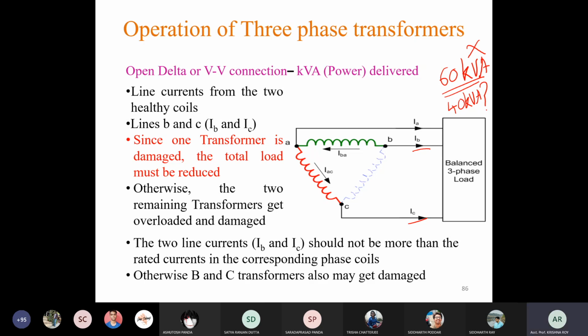So if we supply the previous amount of line current, that means the line current required to supply 60 kVA, then that same amount of line current will flow through the remaining two phases, and that is not permissible because their insulation capacity does not permit that. If we still supply 60 kVA of load, the value of current will be so high that these two transformers will get damaged.